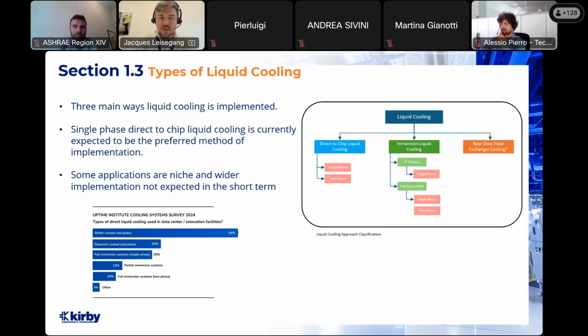Within immersion cooling, you can have the IT chassis within the rack submerged or immersed in a liquid cooled solution as a single phase, and then you can get an open tub or bath immersion cooling either as a single phase or 2-phase solution.